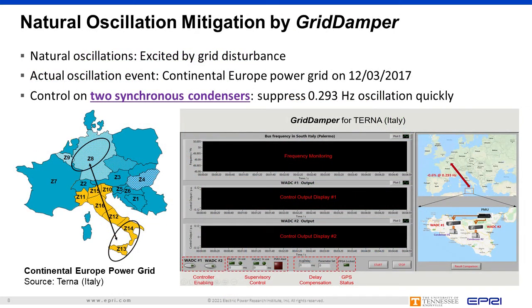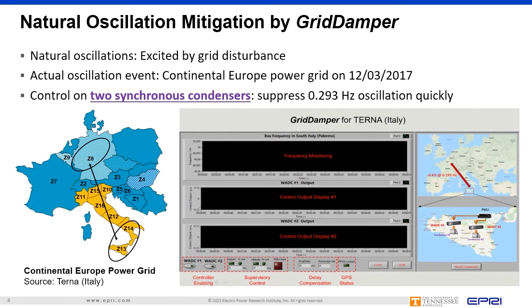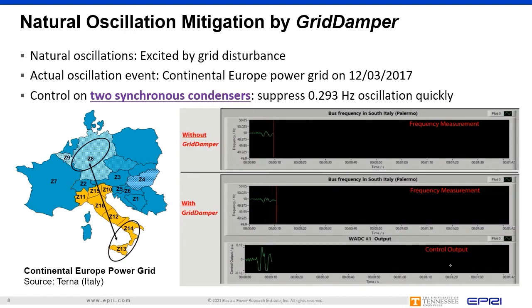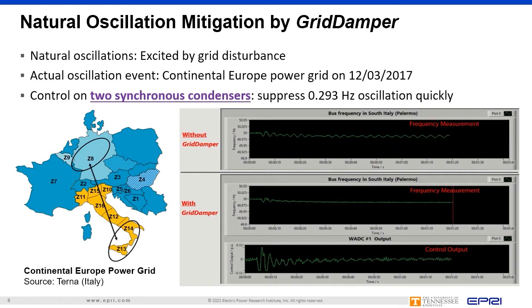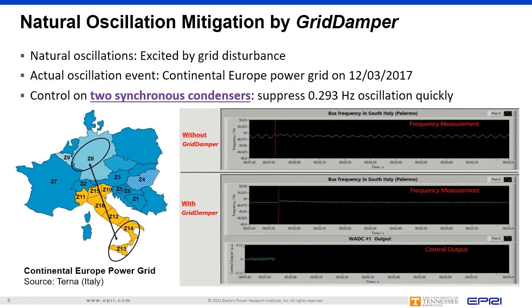The continental Europe power grid experiences a 0.293 Hz natural oscillation between the north and south. An actual oscillation event that happened in December 2017 was replicated to verify Grid Damper's performance. The oscillation was triggered by two consecutive generator disconnections within four minutes. Grid Damper detected the natural oscillation and activated two synchronous condensers in the south.